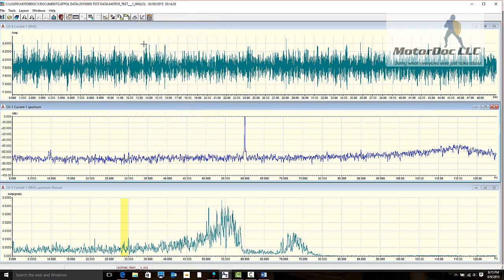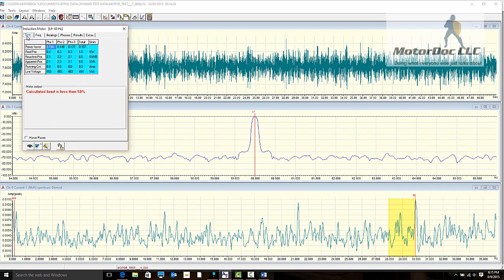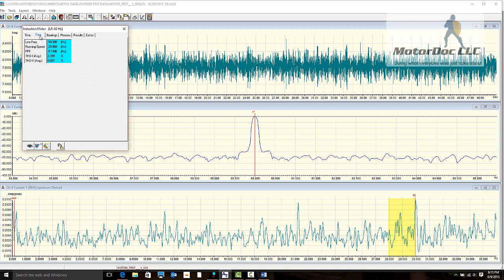I can come in now and click this button and it will do me a quick analysis. It says the load is a little low, so it cannot calculate certain things such as my efficiency and so on. But in here I can take a look at the current, including the power factor, the real power, which is the power of the shaft, the reactive power, which is the power to energize the fields, the apparent power, and then also my voltage and current. I can switch this over to horsepower if it's easier to understand that.